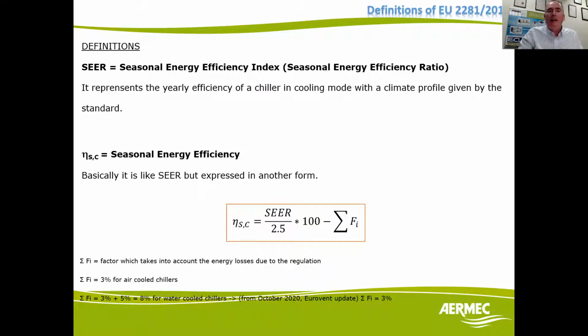The ESEER was a little bit more comprehensive because it took into consideration your part load efficiency, but typically it was based on 4 sets of ambient and 4 sets of conditions. So you had your running at 25%, 50%, 75%, 100%. It was what's called a weighted formula because it assumed a lower ambient as the loads were dropping. So that's what we used for many a year, but they've changed it again. And now we have our SEER, which is much more comprehensive. It's basically taking into consideration every single degree that we're going up in relation to the ambient.